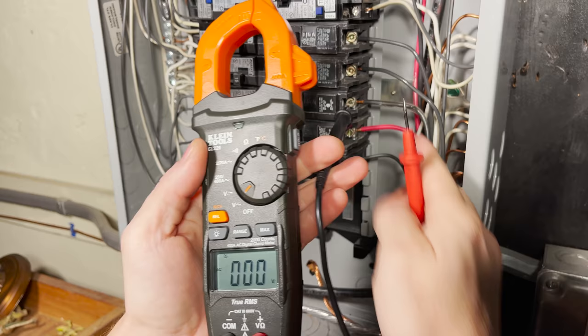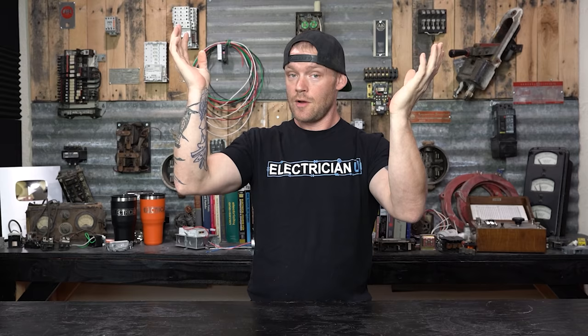Lastly, the first thing you're probably going to do in the field to figure out whether a breaker is bad — if it's a standard general-use breaker — is use your multimeter. Go from the terminal where the conductor is hooked up to ground or neutral. If you have a two-pole breaker, like a 220 load, you should have 240 volts between the two poles, or 208 depending on your wiring system. If you get something weird like 120 volts, and then you take one of them to ground and find zero volts, that breaker is not actually putting out any potential. It's not allowing current to flow because there's probably a gap or the contacts aren't making a connection anymore — so that breaker needs to be replaced.